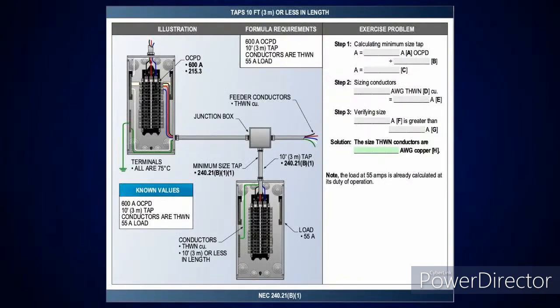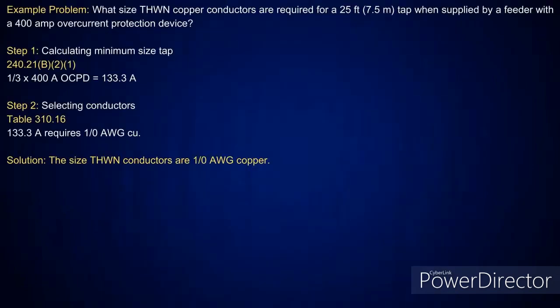When I get over here to the next one, you're going to see we have a 600 amp upstream. Same thing as the last one. I divide by what? 10. Simple. Okay. Now I go to a 25-foot tap. I said, all taps that are more than 10 foot, what do I take it at? A third. So I take a third of a 400 amp overcurrent device. That gives me 133.3 amps. Go look in the 75-degree C column in table 310.16. The next size above that is a 1-aught conductor, which is good for 150 amps.